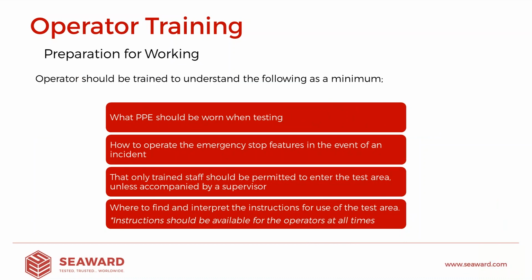So firstly, let's talk about preparation for working. As an operator, they should be trained to understand everything about the area itself. So when they enter the area, what PPE should be worn. So if there are any requirements from a health and safety point of view, and that could be external to the electrical safety testing, so things like high visibility jackets, but looking more into the safety testing, if they are required to wear high voltage gauntlets or maybe goggles to protect their eyes during the testing, that's the first step.